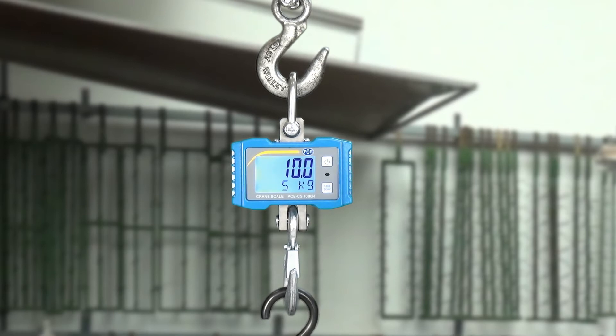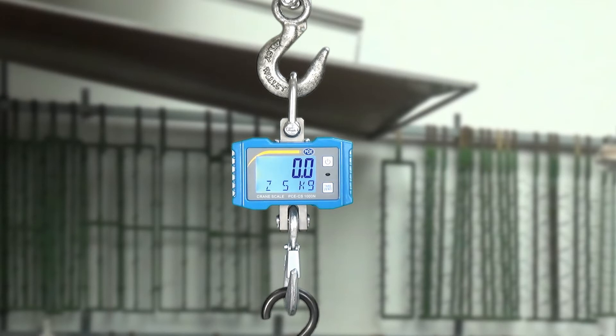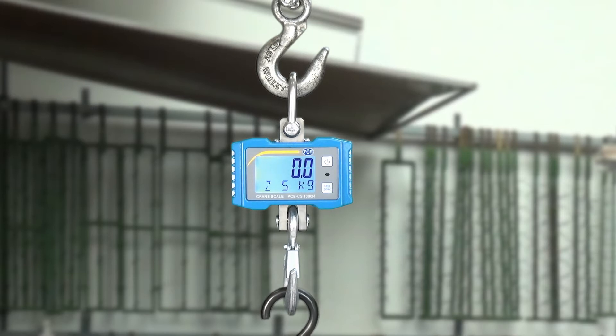The zero value is similar for the user, identical. Because a longer pressing of the zero button causes also a 0 in the display. But I can't change back this function. Means that the load which is zeroed is not in the internal memory.